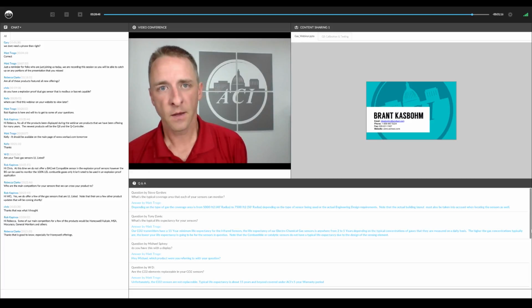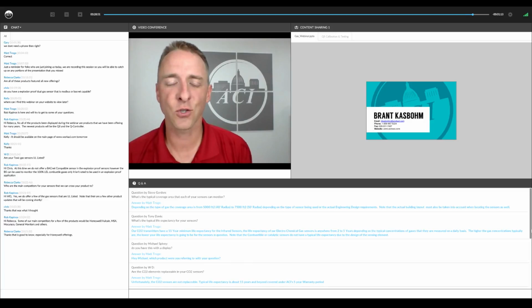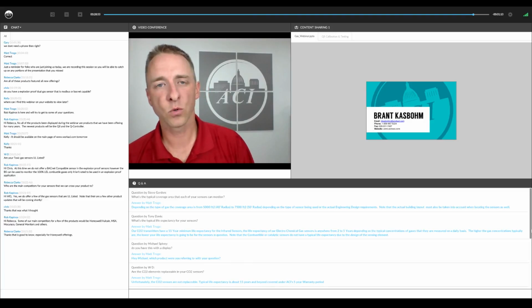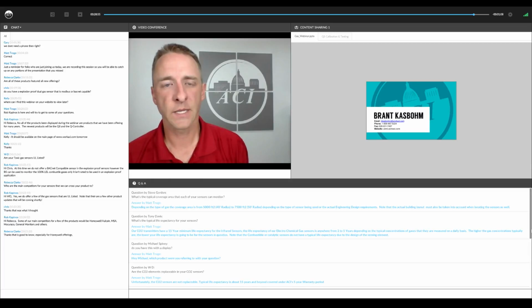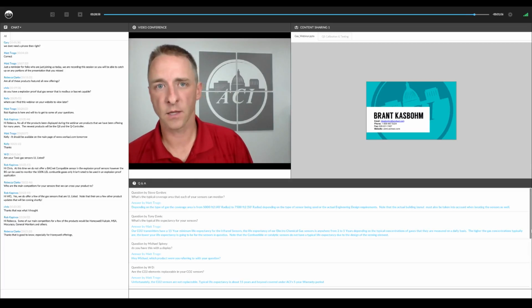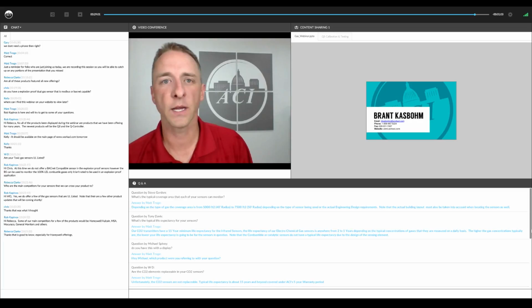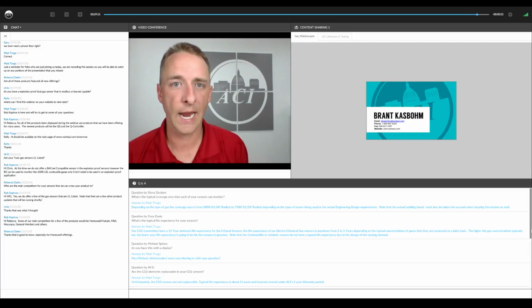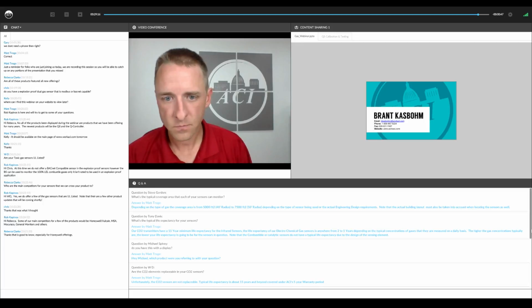So we recommend that people go to local gas supply or welding supply stores or places like Air Gas or Praxair, and then they can either get an inert gas like nitrogen or argon, or they can get the specific required calibration gas, whether it's CO or NO2. You can get those from those types of places as well. A question about NO2 and CO mounting height. I believe we answered that one already. And I don't see any other questions presently in the queue.